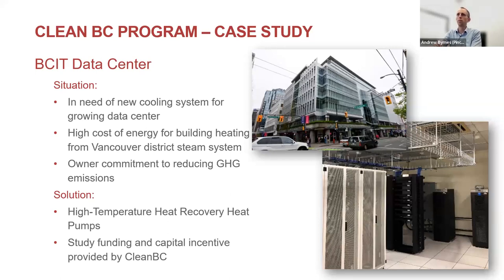The first one is for British Columbia Institute of Technology, at their downtown campus. They needed a new cooling system for a growing data center in this building. The building was also tied to the downtown Vancouver district steam system, which has a very high cost of energy compared to natural gas or heat pump heating. So anything we could do to save steam purchases had a very good payback for the client in energy cost savings. The owner was also committed to reducing GHG emissions through this project. The building doesn't have natural gas boilers, since it's serviced by steam from the downtown system, but because that's a natural gas fired system, it was eligible under the CleanBC program due to the carbon emission savings we could achieve.